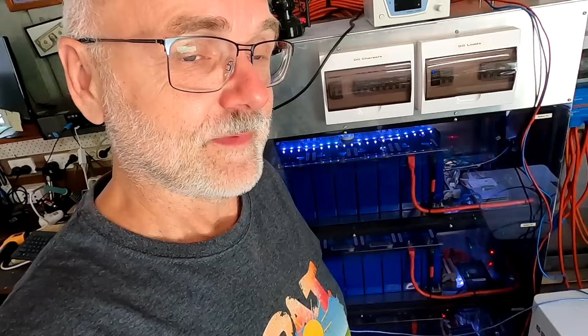So you would need a balancer with 50 amps of balance current. If my load is 100 amps, you'd need a balancer with 100 amps of balance current. As you can see, while this method works in theory, it is not practical. It works with very small loads - if you only have a load of 1 amp, a 1 amp balancer would do it, and we could prevent this cell from triggering the BMS.